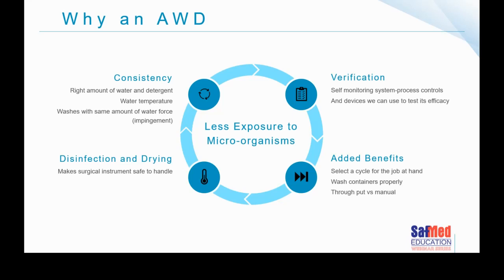At the end of the cycle, your instruments should be coming out of the washer disinfector dried — assuming you haven't adjusted the cycle parameters. When the installation happens, we sometimes say it can't take 55 minutes, it must come out much faster. Then we adjust the parameters, which is really not a good thing. The whole idea is to make these instruments safe for us to handle while preparing sets. We want to disinfect them so they are safe for us — and this disinfection cycle and process will kill COVID-19.